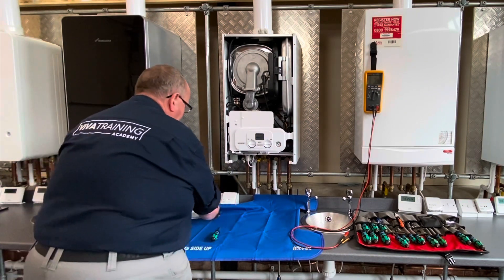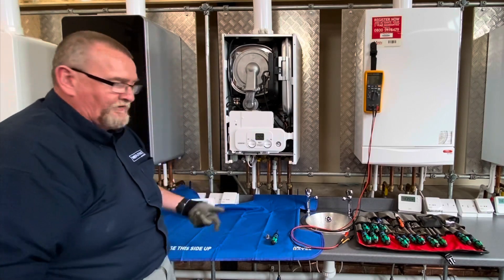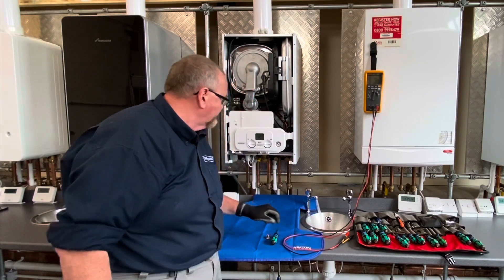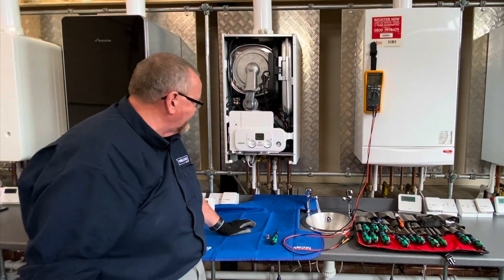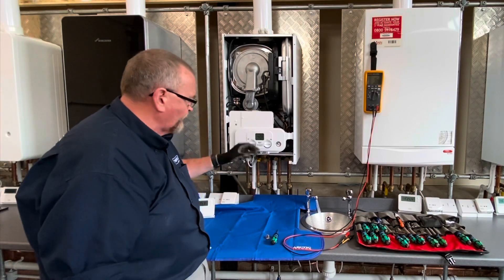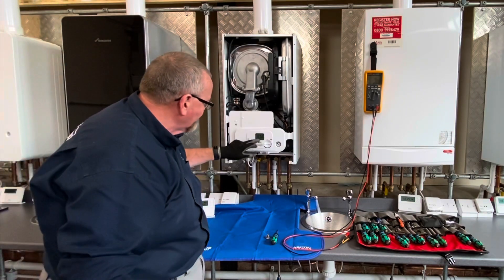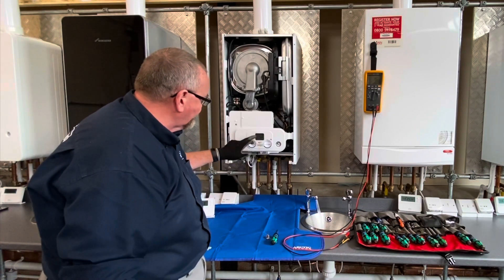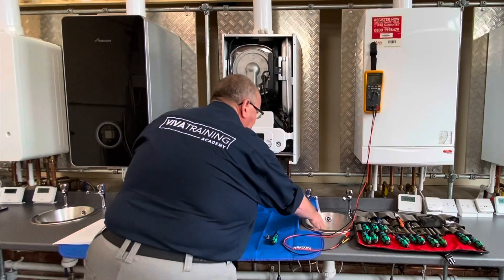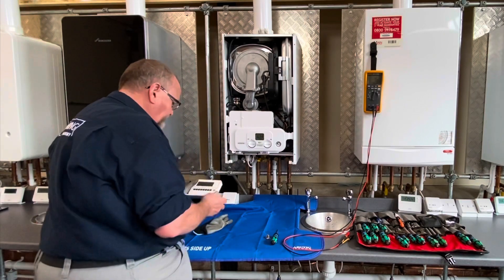Power back on. We've got a little bit of communication, the front screen has come up and the boiler's going through its start-up check. We're going to turn the hot tap on and see if it's working. Both thermostats are up to maximum. Turning the hot tap on - the tap symbol is flashing, we know we've got a demand. The little flame symbol has come on and we're up and running. We'll give it a minute or two to warm up. We can hear the boiler ramping up to high, the water's nice and warm. So we'll turn that off.